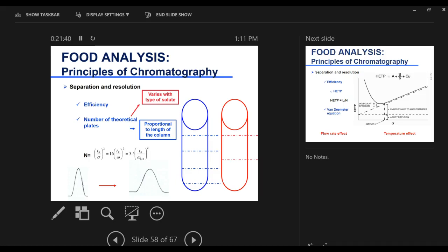Or you have more pores because you lose particles from your stationary phase or dissolve into your mobile phase. Then you have empty spaces in your column, void. Then your compound of interest is going in and kind of being lost inside of the column. So it takes longer for it to reach equilibrium. So over time, my number of theoretical plates go down. Okay? So I kind of lose efficiency over time.